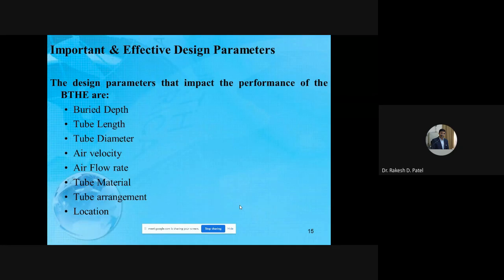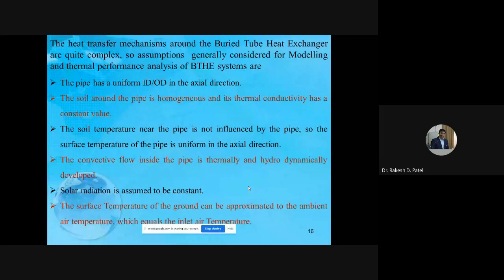So buried depth, tube length, tube diameter, air velocity, air flow rate, tube material, tube arrangement, and location. These are the very important or effective parameters for the design of this heat exchanger. Now, the heat transfer mechanisms around the buried tube heat exchanger are quite complex. So some assumptions are generally considered for the modeling and thermal performance analysis of these heat exchanger systems.